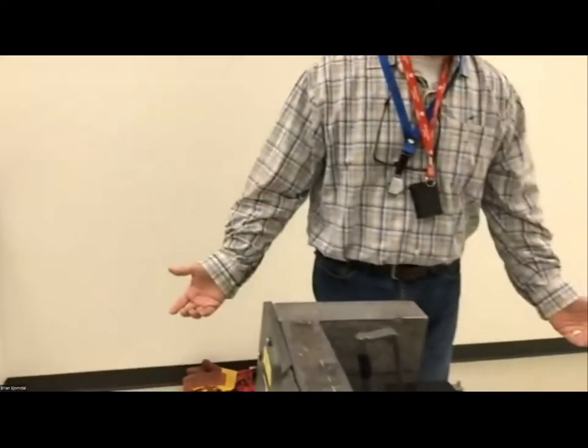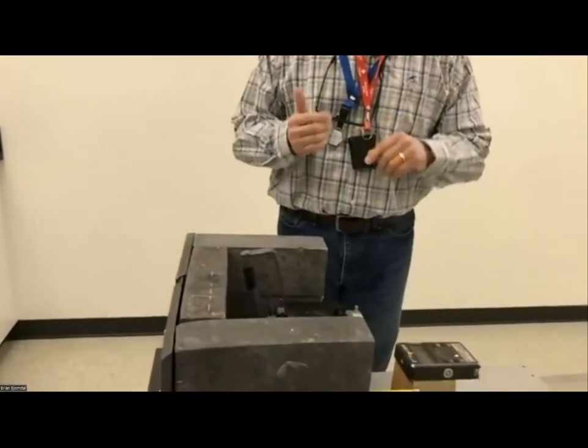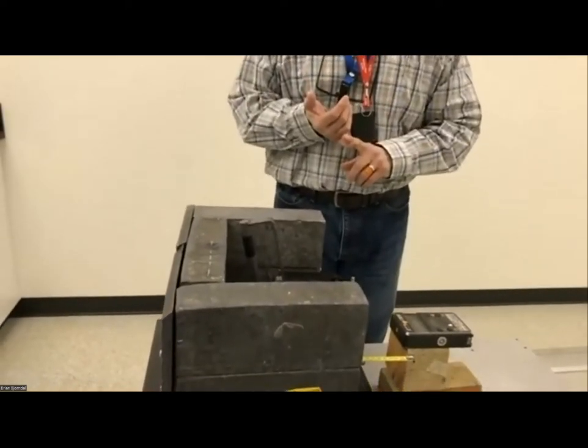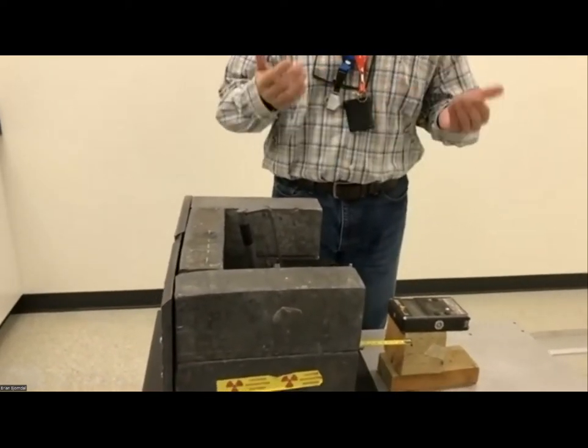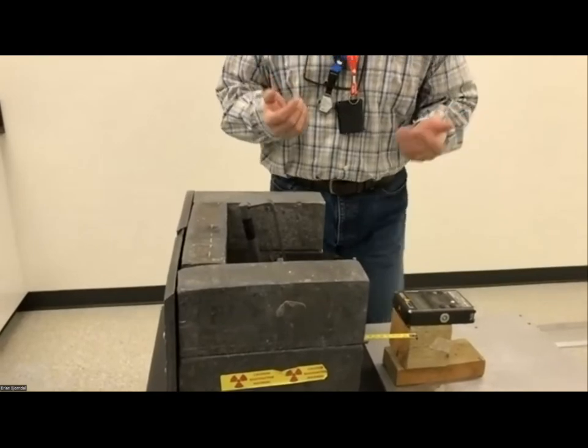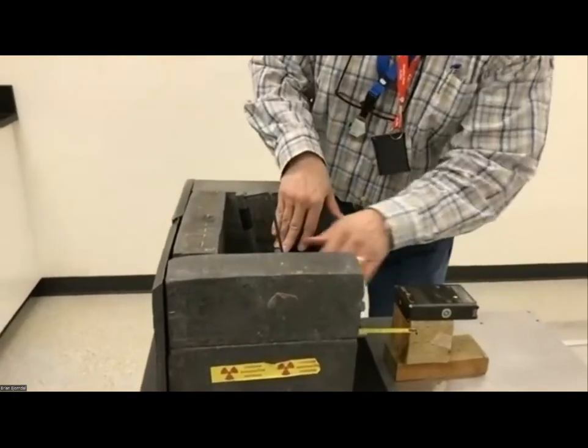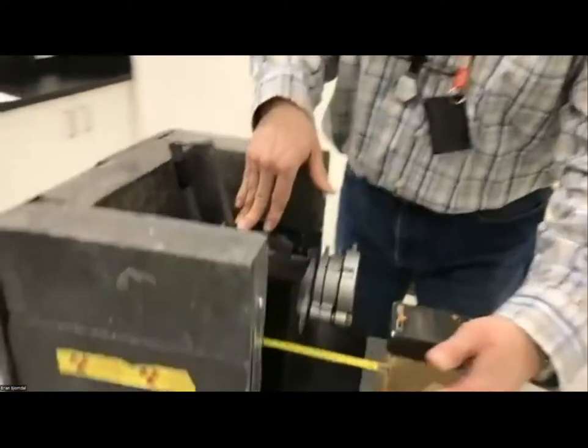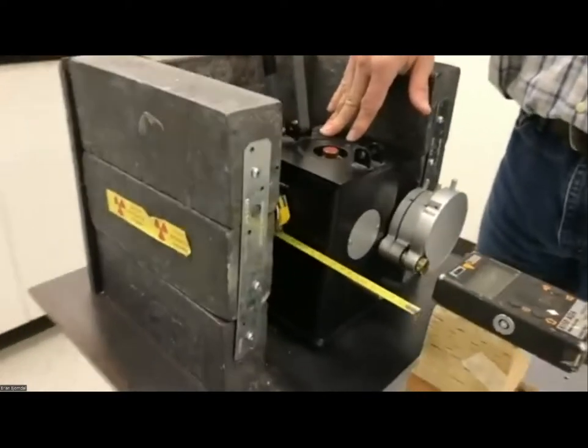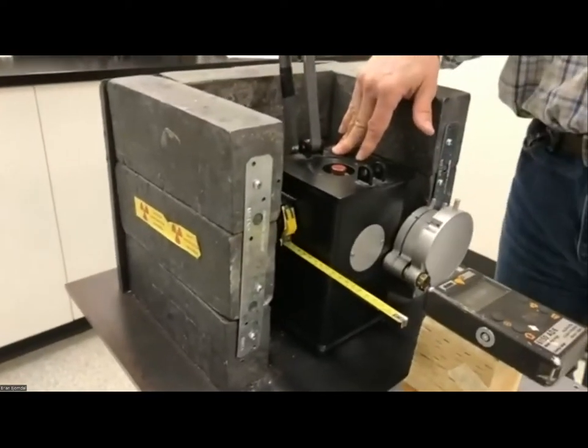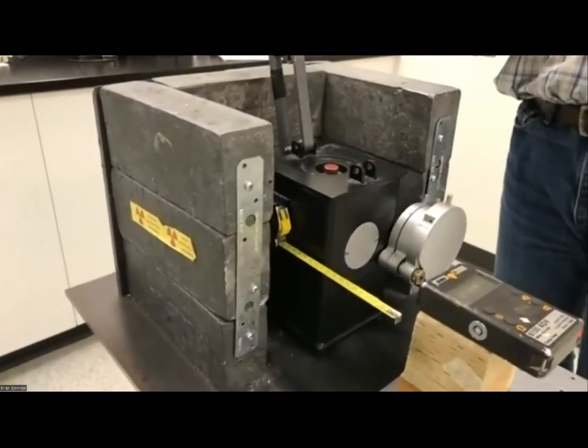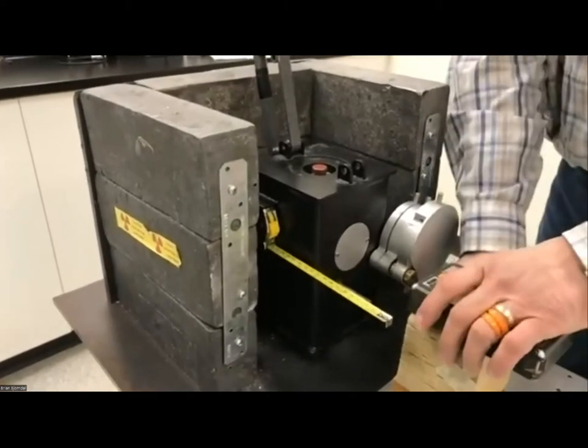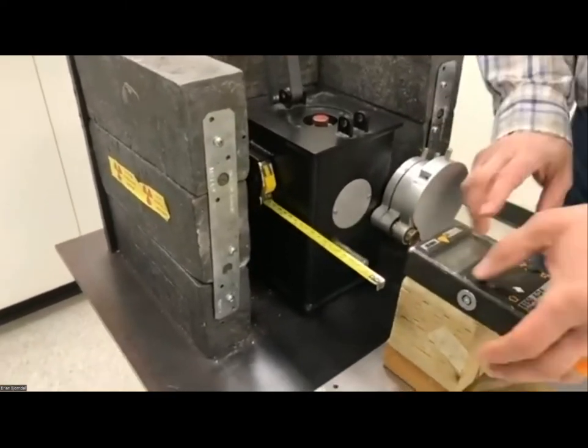So we've got a setup here. When we set up these instruments, we use a small application to set the desired dose rate based on the instrument, up to 10 millisieverts per hour. This instrument calibrator is fitted with a tape measure, and we have an external one as well. We can set it at the desired distance to achieve a certain dose rate. So this one is an Automess 6150. We're going to turn it on here.